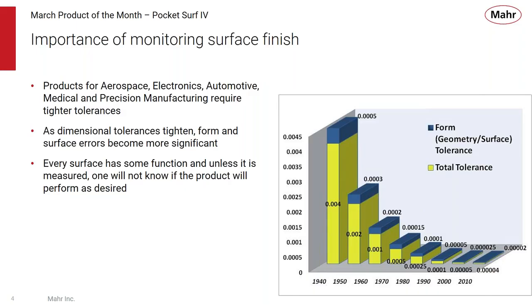So every surface has some function, and unless it is measured, one will not know if that product will perform as it is desired. You can see this chart on here represents how tolerances have gotten smaller and smaller since the 1940s and 50s. And even a small form or surface finish error can be a big percentage of the tolerance and affect how that part performs. So it's important to monitor surface finish these days.